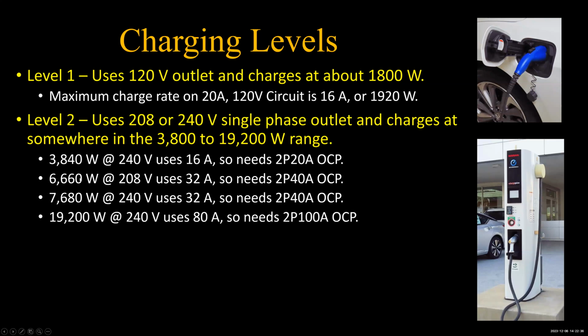Level 2, there's a lot of different level 2s out there. They go all the way from 3,840 watts, which is 16 amps at 240 volts and runs on a 2-pole 20 amp breaker, and it goes all the way up to 19,200 watts, which uses 80 amps, which requires a 2-pole 100 amp circuit breaker. For the moment, that's the biggest I'm aware of. They might be making some bigger ones at level 2, but we'll see what various sizes of level 2 will do in terms of charging times in just a minute.